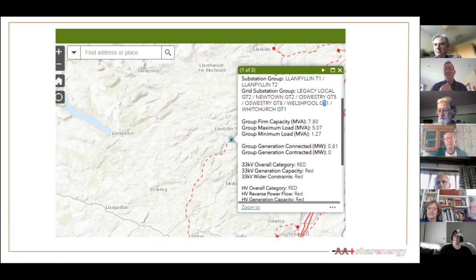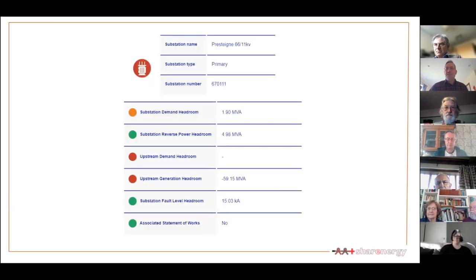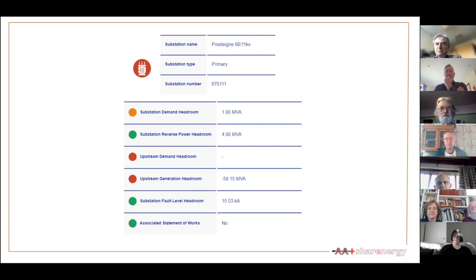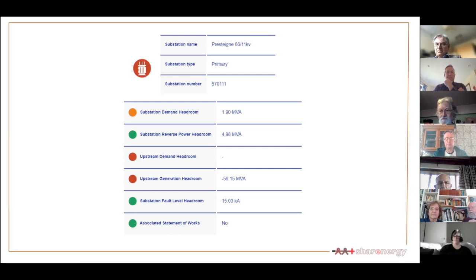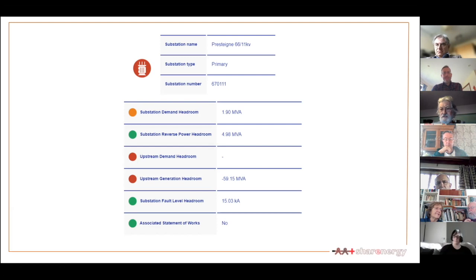Alison asked for an explanation of terms like headroom. MVA is essentially measuring amperage but you can transfer that almost directly into megawatts. Headroom is simply how much capacity is there. It's saying there is room to connect another 1.9 megawatts for demand but there's not room to connect any more generation. This is about export — feeding into the grid — so this is where a grid-connected solar farm, wind turbine, or hydro scheme would bump into these grid constraints.